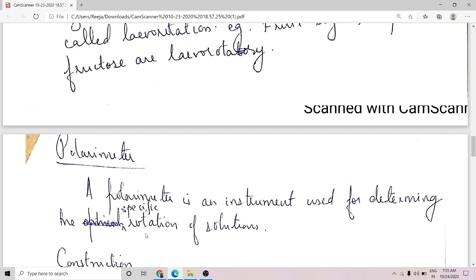What is a polarimeter? A polarimeter is an instrument used for measuring the angle of rotation of the plane of polarization of plane polarized light when it passes through an optically active substance. From this measured angle of rotation, we can calculate the specific rotation of the solution.